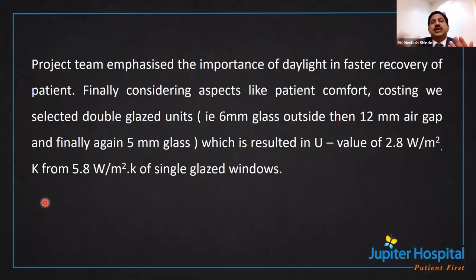Our project team came to the conclusion that if I use 6 mm glass outside, a 12 mm air gap, and again 5 mm glass, a double glaze glass, it can reduce the U value from 5.8 to 2.8. So just by doing this, we are not compromising anything on patient satisfaction, which is very, very important when our ideology is patient first. In our hospitals in Thane, Pune, as well as Indore, in all areas where critical patients are there, direct sunlight is coming into the rooms. So this was for the glazing.